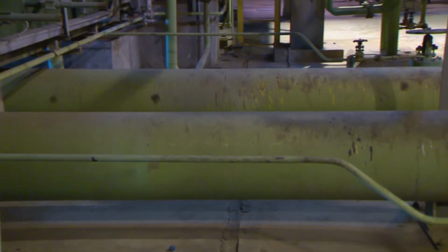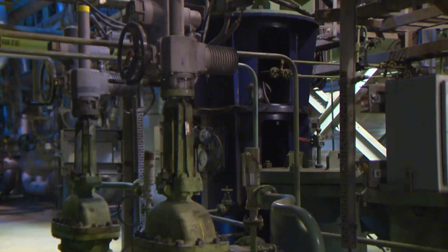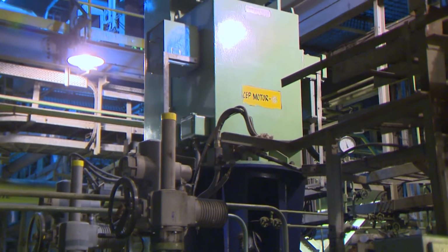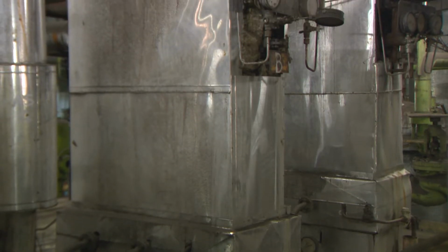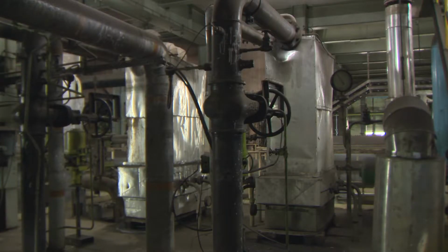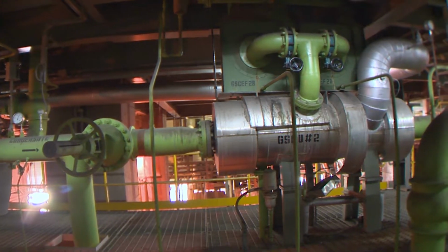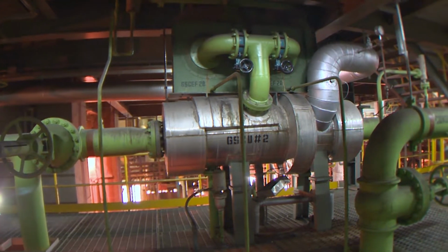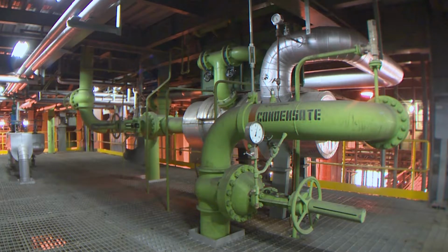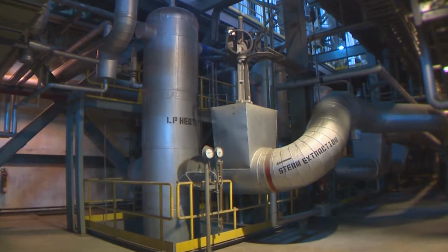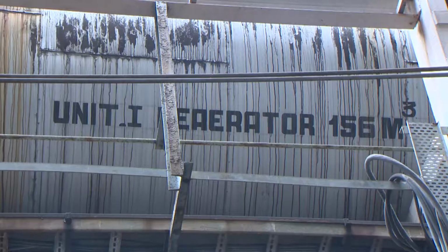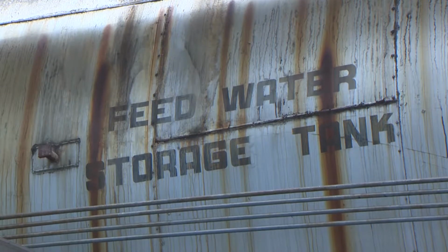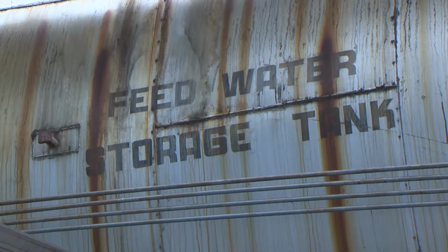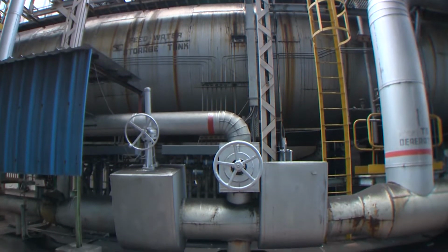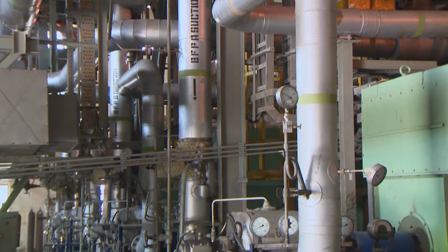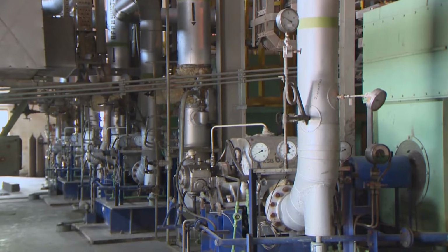The main condensate from the condenser hot well is pumped to the deaerator by means of the condensate extraction pump. The ejector creates vacuum inside the condenser by sucking air and non-condensing gases from the condenser. The gland steam condenser condenses the turbine gland steam and the leak of steam from turbine valves. It is located after the main ejector. Then, the main condensate passes through low pressure heaters where the temperature is raised and then goes to the deaerator. The deaerator removes dissolved gases in the feed water in order to avoid corrosion in boiler water tubes and drums. The boiler feed pump sucks water from the deaerator and feeds it to the boiler through high pressure heaters.